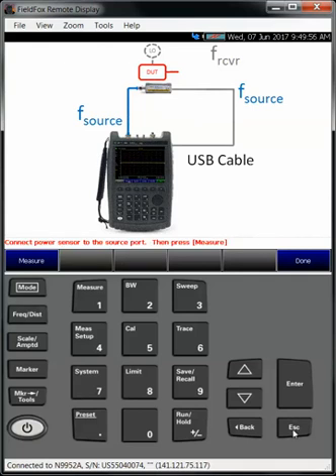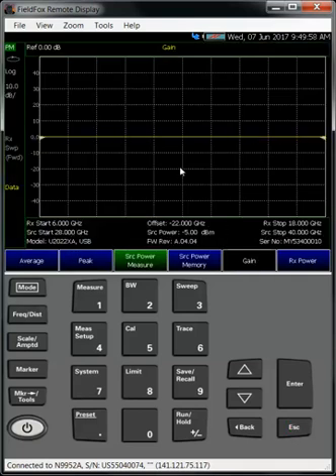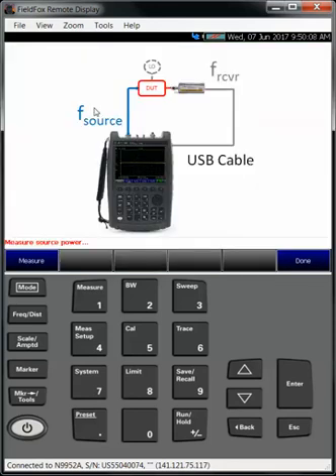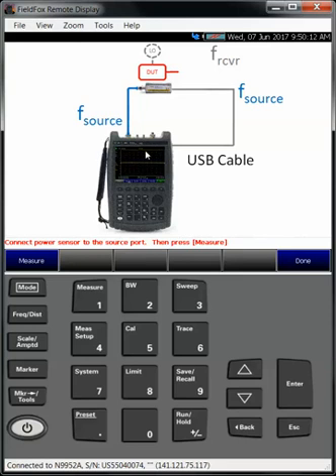And I just did this a few weeks ago with a converter, for a satellite converter, and the numbers matched very well with other systems. So I'm confident that the measurement is accurate and it works. I also want to point out that it's important to pay attention to harmonics. This is a broadband sensor. FieldFox source does have harmonics and subharmonics, so you want to look at your input frequencies on the spectrum analyzer. You want to look at your output frequencies to be aware of what your broadband power sensor is measuring. And that's it.